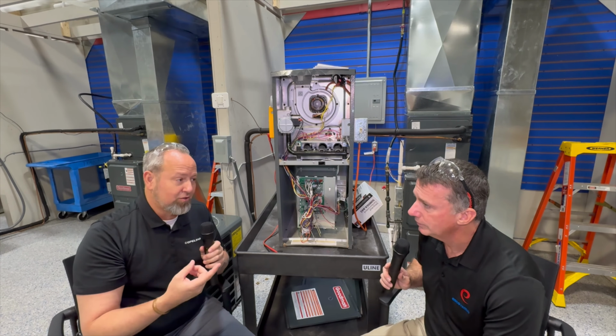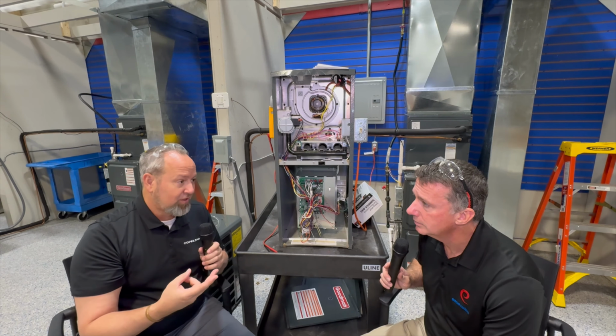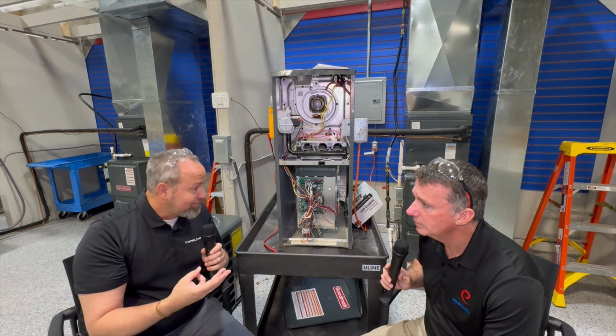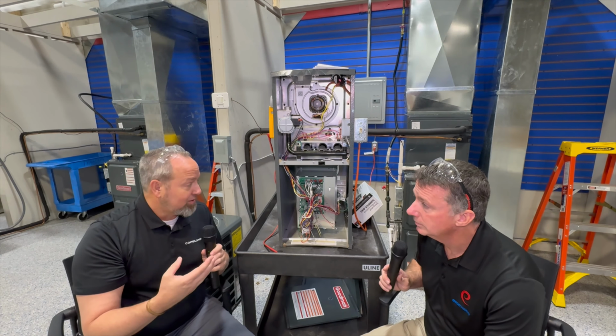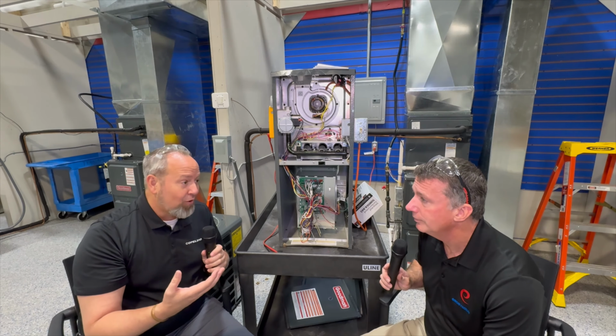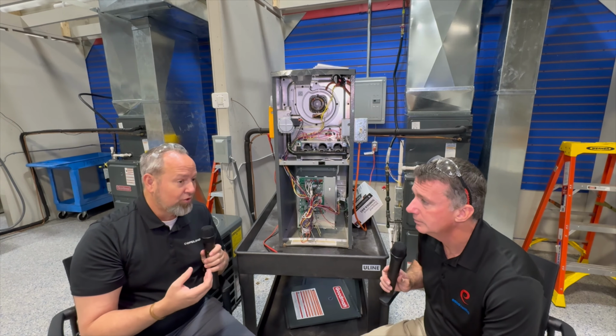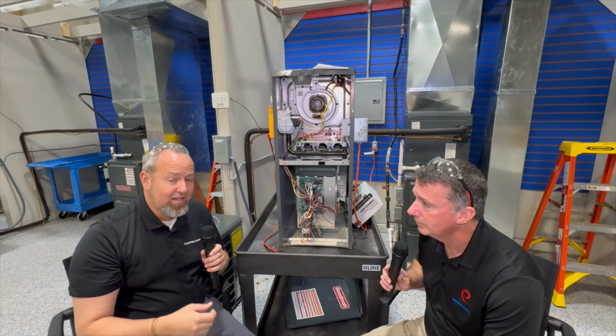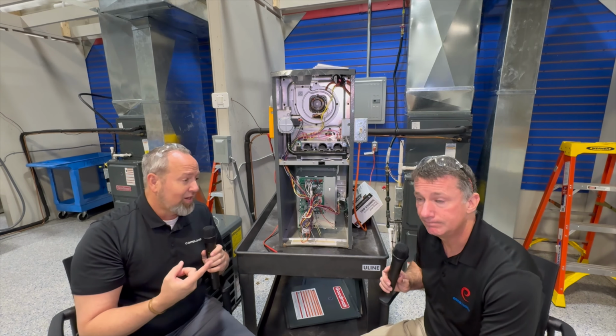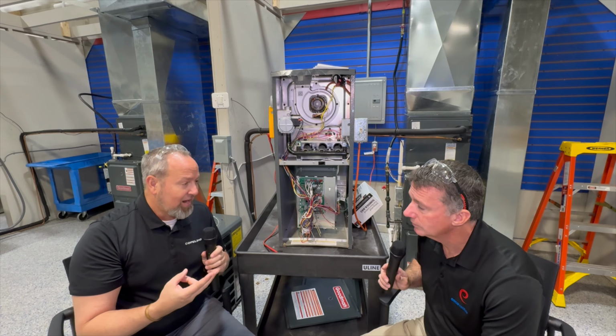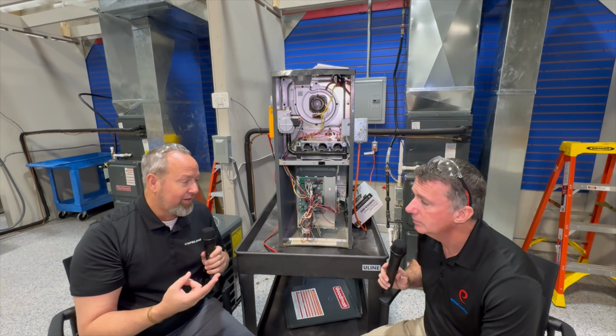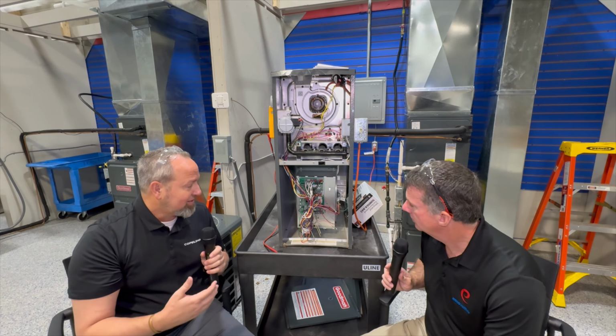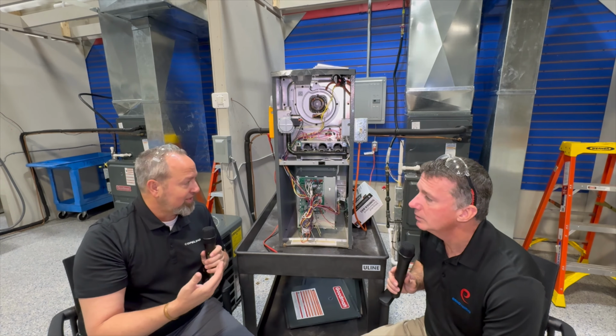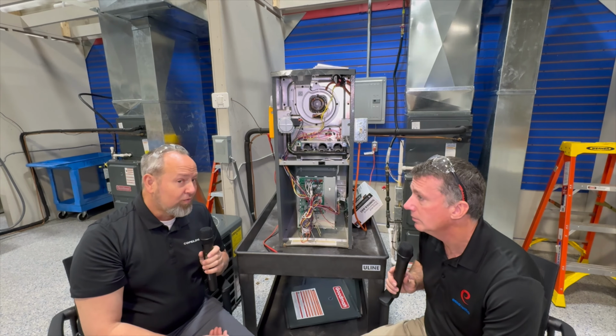It's running the limit circuits, has the pressure switch circuit in there, sometimes the flame sense circuit, and sometimes the 24-volt power is going in through that plug as well. So one plug and you have everything tied together. It's faster as well as more accurate, and you're not having to worry about miswiring something. So that's kind of the evolution we've seen with these boards on the low voltage side.